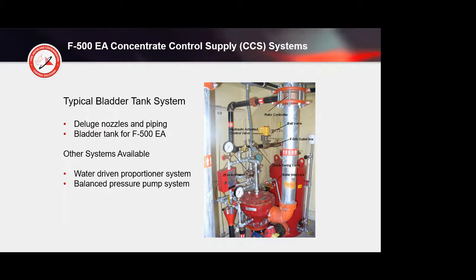Early on, the very first system that was ever installed used an Ansul bladder tank, but the customer insisted on using F500 Encapsulator Agent. It was for a hydraulic pit press. It was a 3-dimensional Class B fire. When it caught on fire, they couldn't put it out with water. They couldn't put it out with foam. And the fire department showed up with F500 EA and instantly put the fire out. So when they put the fixed system in, they demanded F500 EA. We weren't even in the business. That was the project that got us in the business.